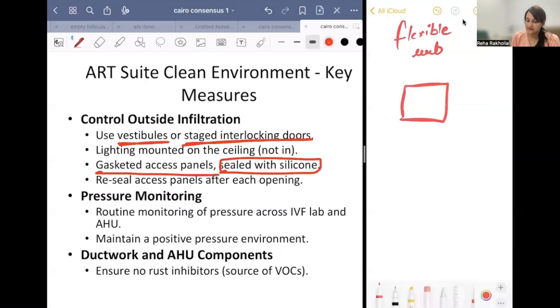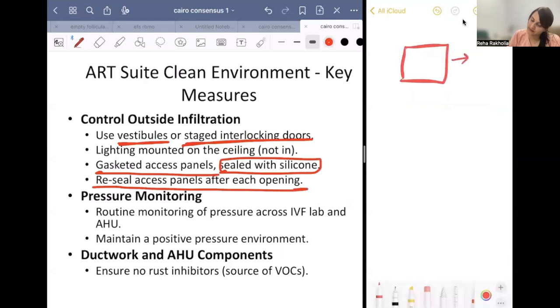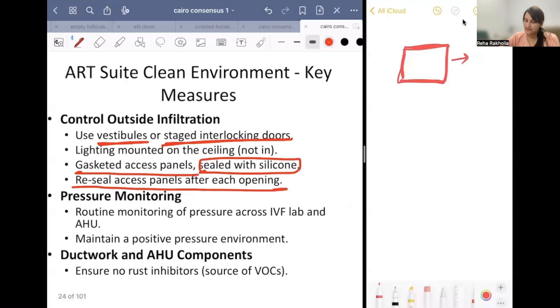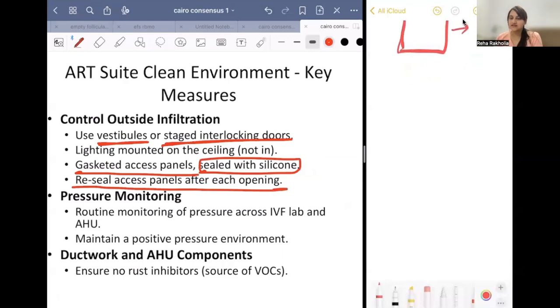Okay. The gasketed access panel is sealed with silicone. Reseal the access panel after opening. If by chance we want to open this access panel to do something, we'll have to reseal it. Then pressure monitoring: maintain positive pressure. The pressure will have to be measured routinely, and we'll have to maintain positive pressure.